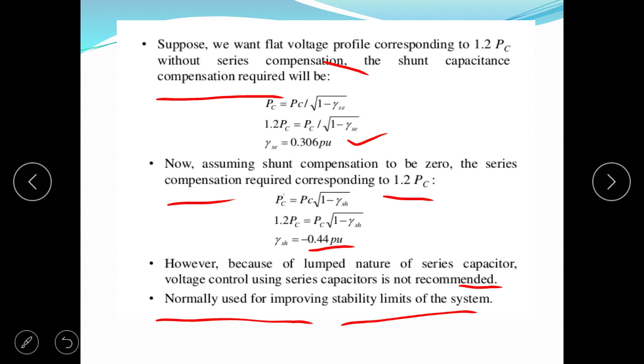It means in case of shunt compensation, we have to decrease the value of reactance up to 56%. However, because of the lumped nature of the series capacitor, voltage control using a series capacitor is not recommended. It is normally used for improving the stability limit of the system. It means series compensation is only required to improve system stability, and shunt compensation is required to compensate the reactive power in the line or to improve the voltage regulation of the line. Thank you for today's class.